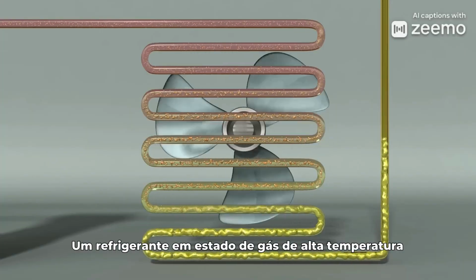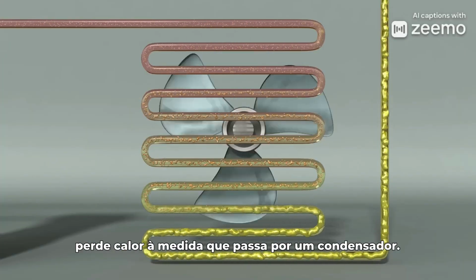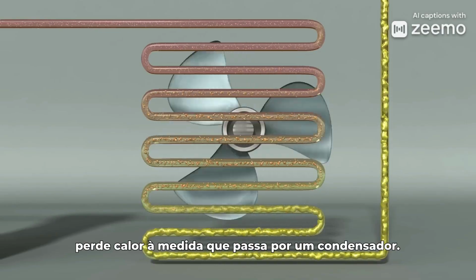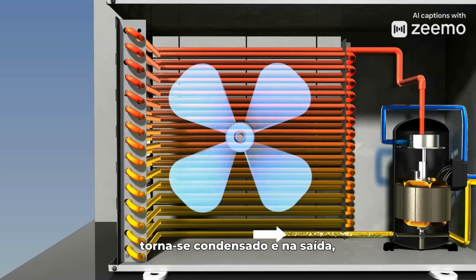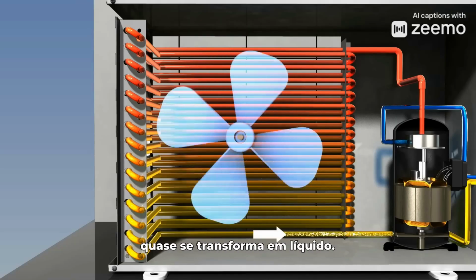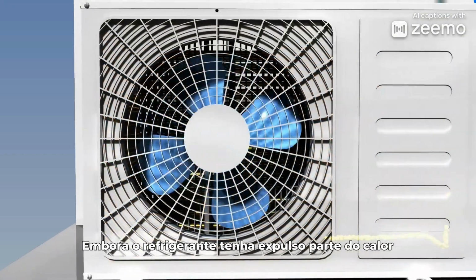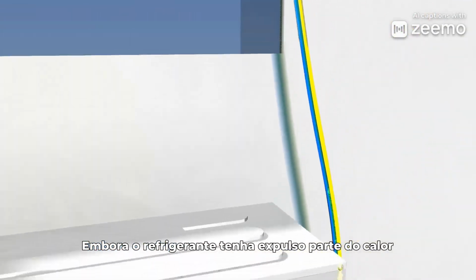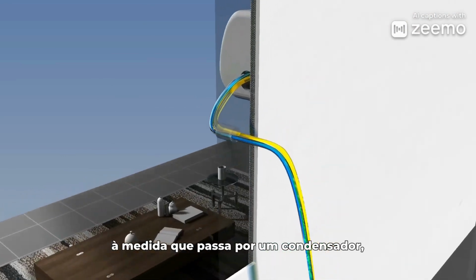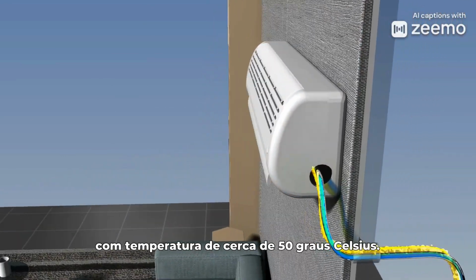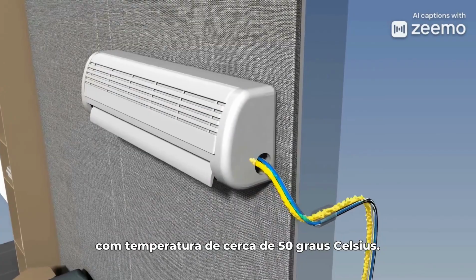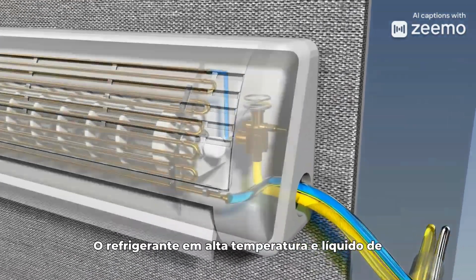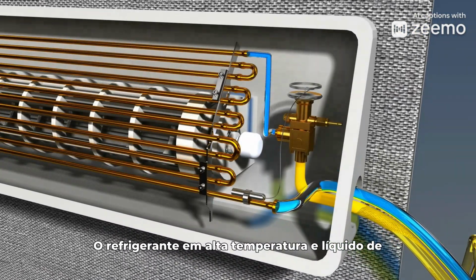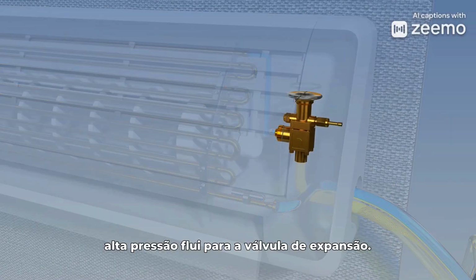A refrigerant in a gas state of high temperature loses heat as it passes through a condenser. As such, it becomes condensed and at the exit, it turns into liquid almost. Although the refrigerant has thrown off some of the heat as it passes through a condenser, it is still hot, with a temperature of about 50 Celsius. The refrigerant in high temperature and high pressure liquid flows into the expansion valve.